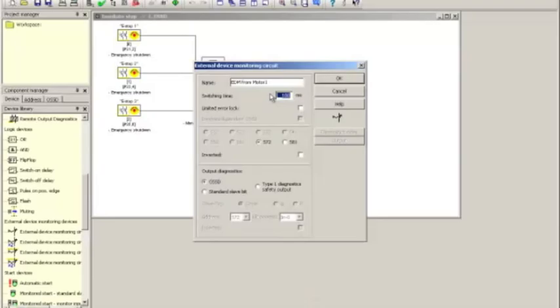What this means is that as soon as the safe output turns on, the safety controller must see an inversion of the feedback signal within 100 milliseconds. That may work for smaller contactors, but it will certainly not work for large contactors where a lot of load needs to be switched. So my suggestion is to do something on the order of one second, 1000 milliseconds.